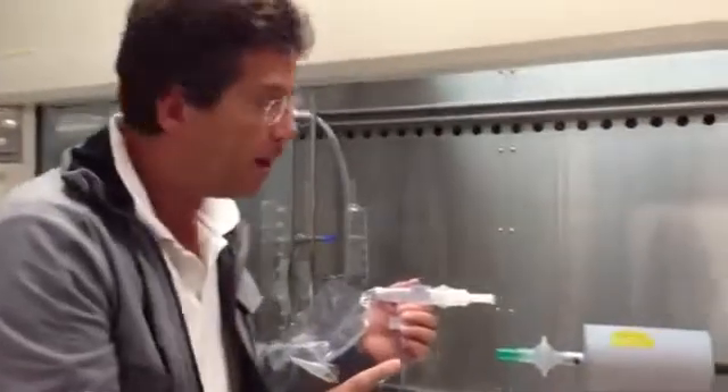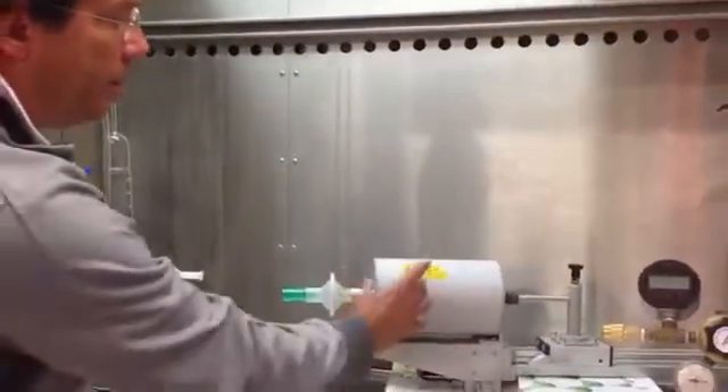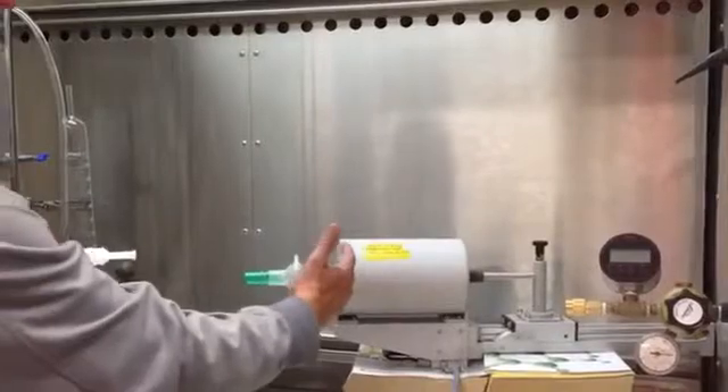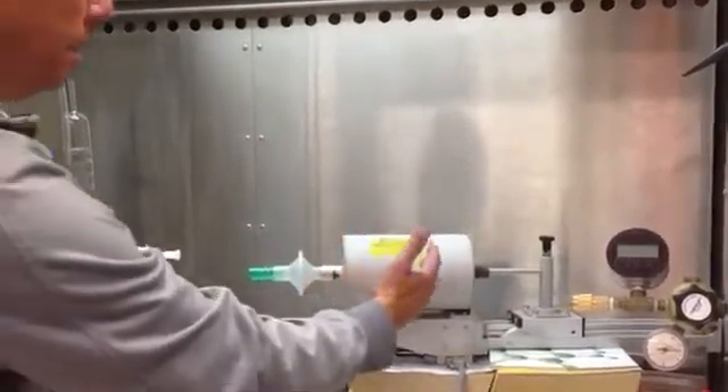We're going to hook that up in a minute to our breathing machine. Our breathing machine is a diaphragm displacement unit. We turn it on — it's going to displace 500 milliliters, 15 times — 15 breathing cycles in a minute. So it's simulating adult tidal breathing.